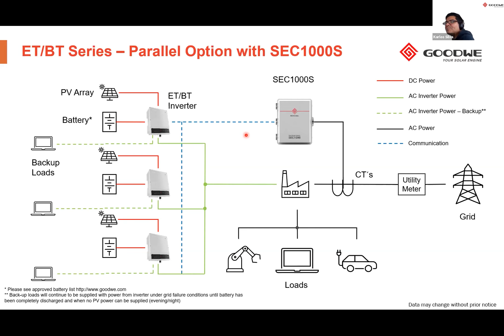So imagine connecting 3 BYD battery towers to each ET inverter. And I think I made the calculation before, if you connected 3 22 kilowatt hour towers to an ET inverter, that gives you 66 kilowatt hours of battery capacity for one inverter. And if you multiply that by 10, it gives you 660 kilowatt hours of battery capacity. And if you take a 100 kilowatt hour daily load profile, then that gives you at least 6 to 7 days of autonomy. So quite a lot of battery capacity that you can realize using a SEC1000 data logger.